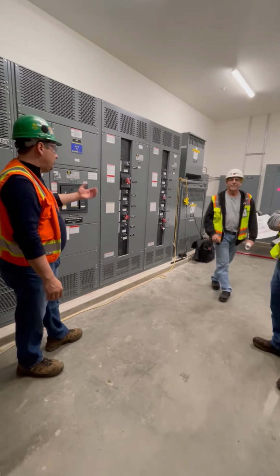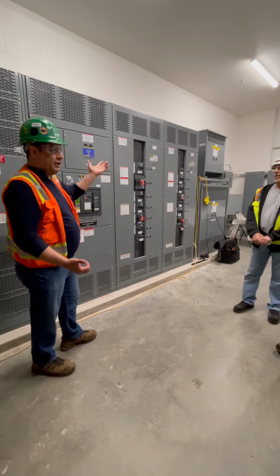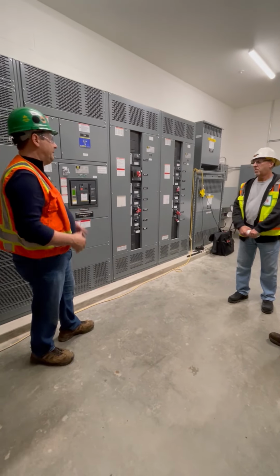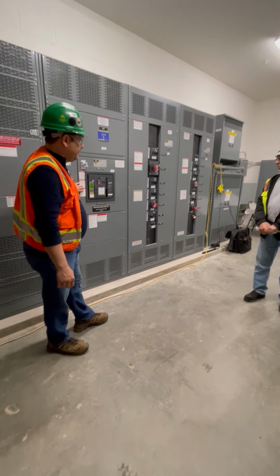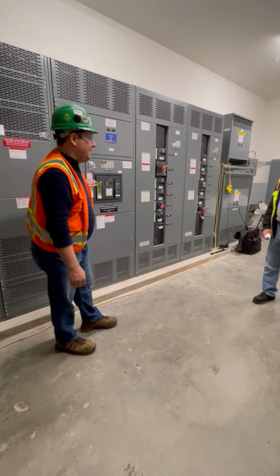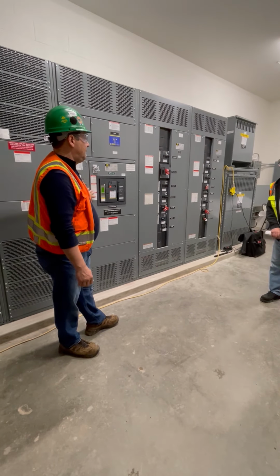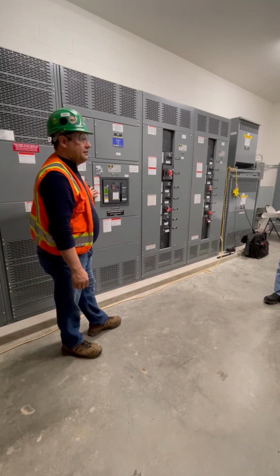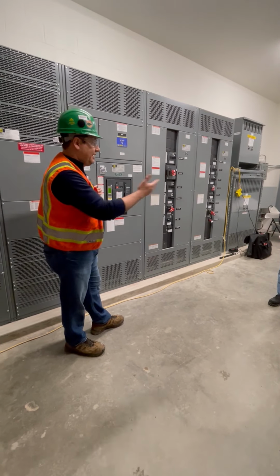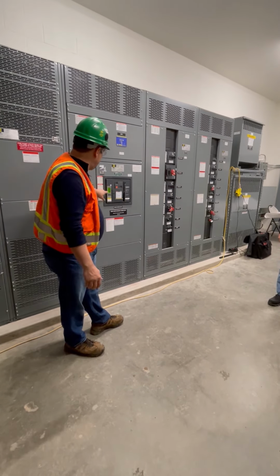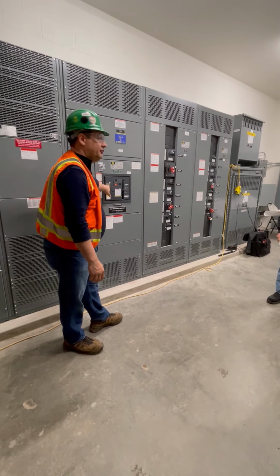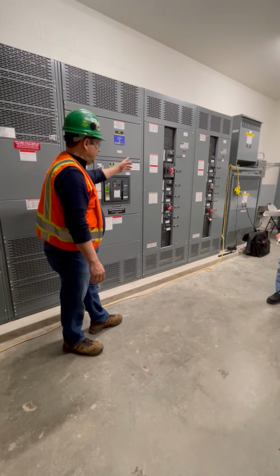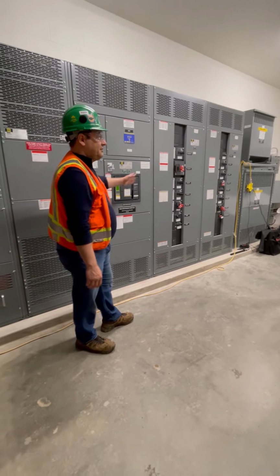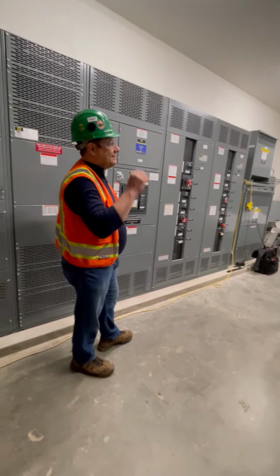Well, at least that way you know you can turn the rest of it off and keep that breaker off until you find the ground fault and fix it. I just want to mention that for operational procedures, right? If that happens, it could create some headaches, especially in the middle of the school day, trying to get everything back online. But keep in mind, if you see that ground fault is on, you tripped on ground fault, that's when you start the process of elimination and try to isolate it.